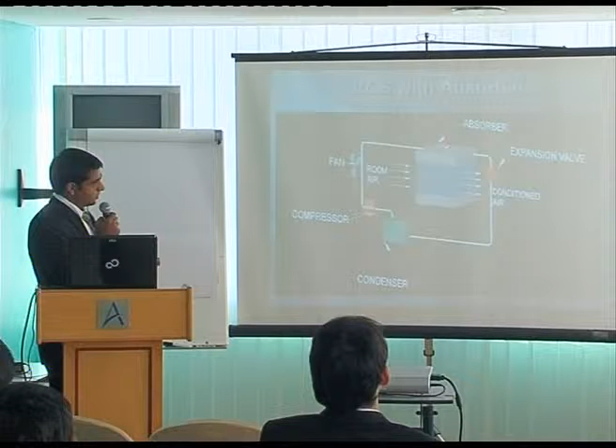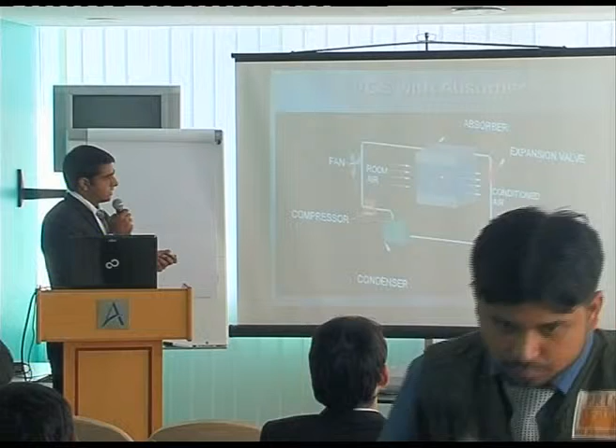The strong liquid desiccant solution is made to flow through the top, through this honeycomb mesh, and it stays there. Room air is blown using a fan from the room into this honeycomb structure, and the moisture from the room air is absorbed by the liquid desiccant because of the pressure difference between them. Once the moisture is absorbed and the temperature is reduced by the evaporator coil, the conditioned air is given out. Hence, we can get the conditioned air at the required temperature.